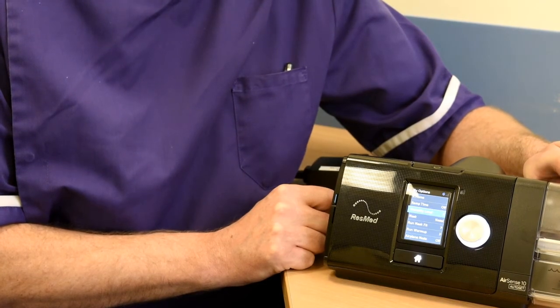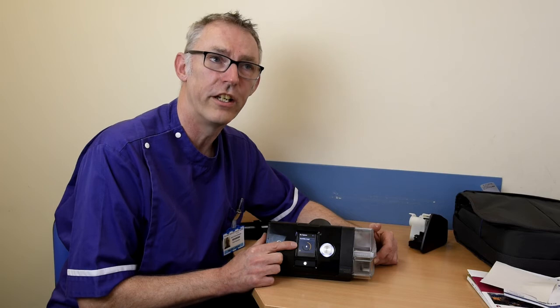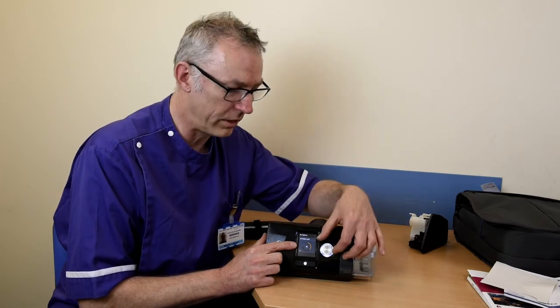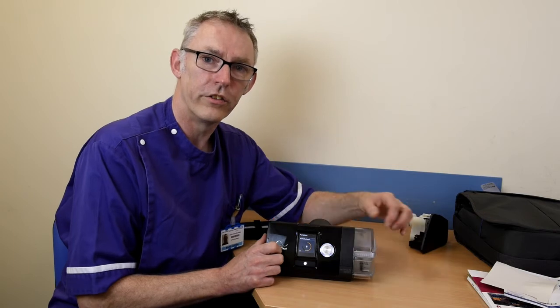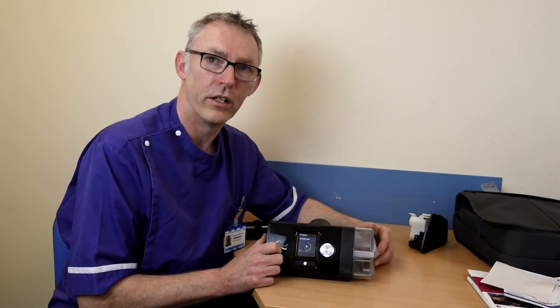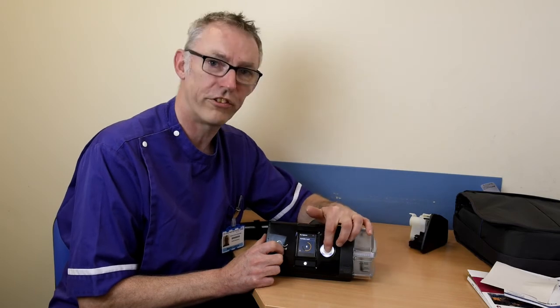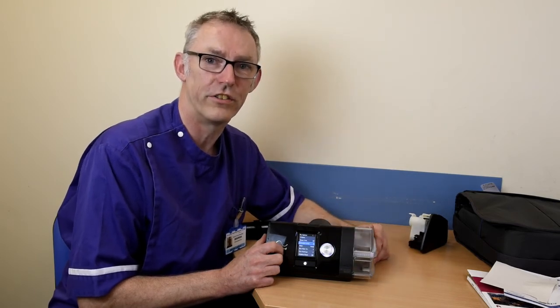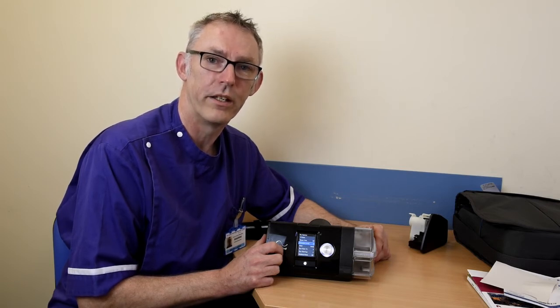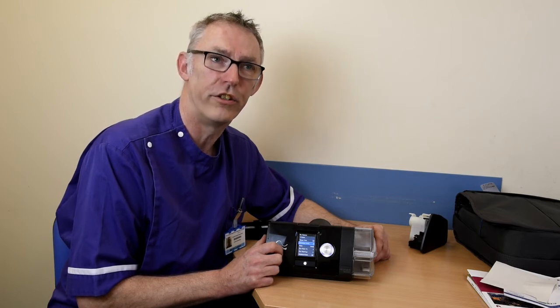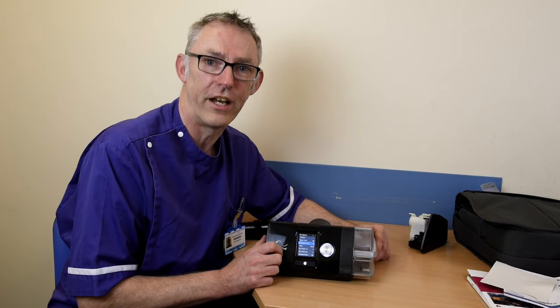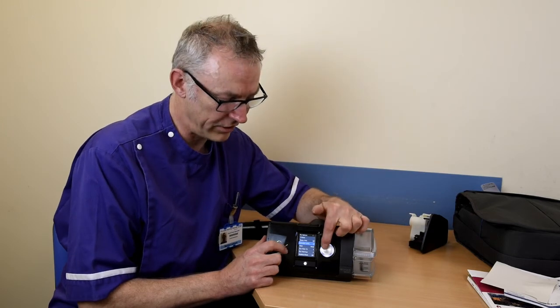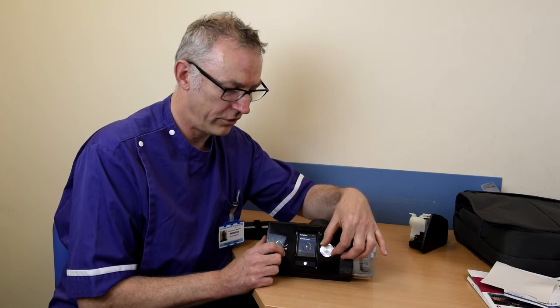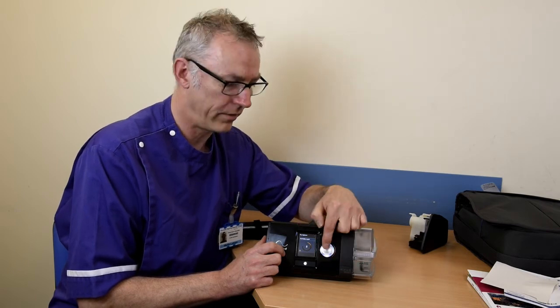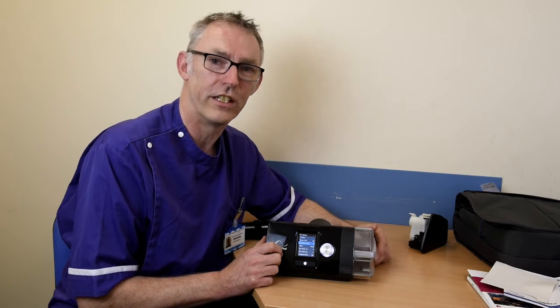If you use it on this setting and find that you are not getting enough moisture, then you need to increase it. This is done by turning the dial to get the number that you require. Once you've set the number you require, you press the dial and this locks it into the device's memory, so that every time you use the device it will be on the same setting. If you find you're getting too much water in your tubing, then you need to turn this down. And again, this is done by selecting humidity level, turning the dial to a lower number, then pressing the dial to lock it in the memory.